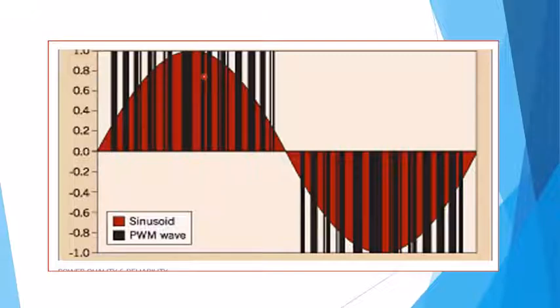So the 4-pole machine will run, instead of 1800 RPM base speed, it'll actually run all the way up to 2000, 2200. The mechanical characteristics you have to really look at, on your pumps and motors, but it is a way to get a situation where if things aren't quite balanced enough, you can bring them back into balance.